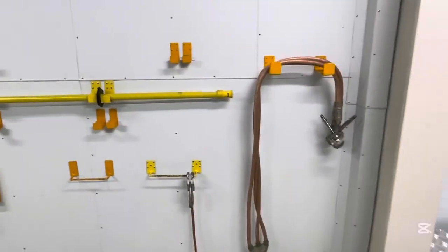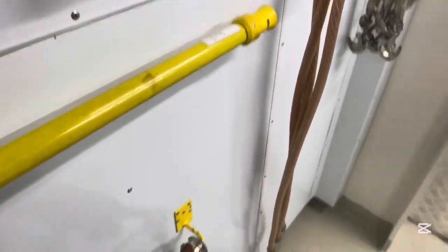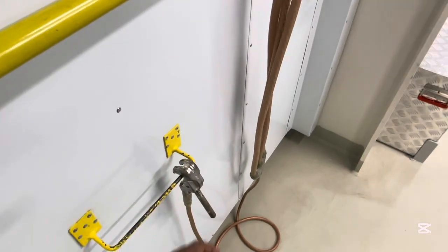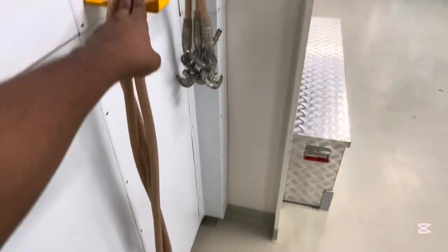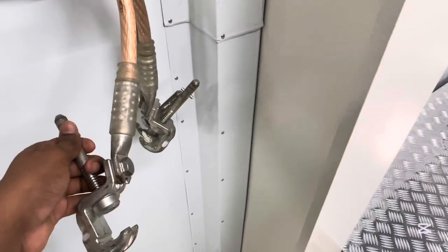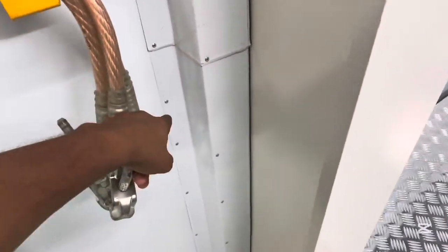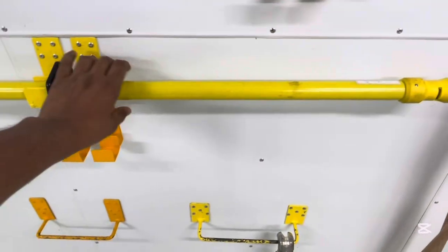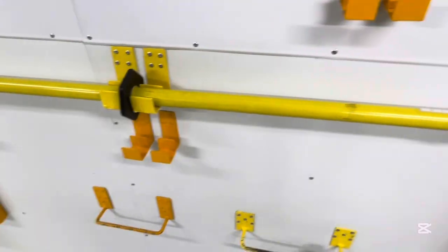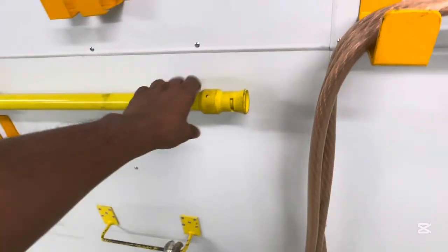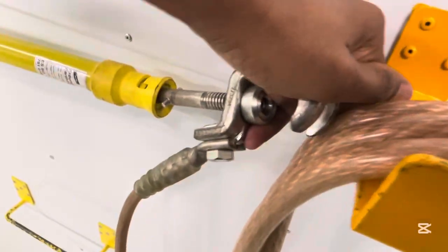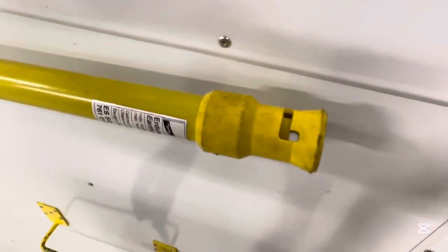The next thing you see in a high voltage room is this spider — that's what it's called. This is also for earthing a particular machinery. When you go to a generator, a bus bar, a shaft gear motor or somewhere similar, you have 3 spiders — a spider with 3 hooks and 1 hook for earthing. To use that spider, you cannot directly use your hand to earth it; you have to use a proper handle. You insert those spiders one by one into this handle, and then you ground it.